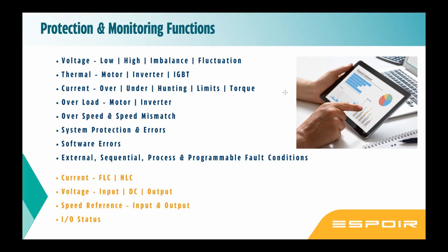For example, when this level is achieved, your VFD should stop. When the temperature is achieved, this should stop or this should start. All that you can program. You can integrate that with the PLC, DCS, HMI, or any of your field instruments. You can change it based on all your analog inputs and control inputs, whatever you have. Now comes the monitoring functions. The general starters don't give this.